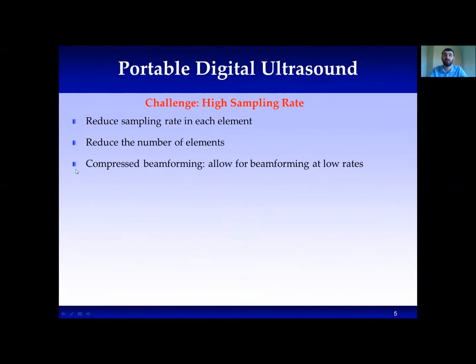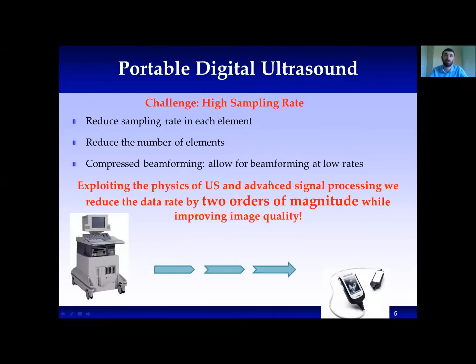However, the main challenge we encounter when trying to fulfill this vision is the sampling rate and the huge amount of data. We reduce the sampling rate at each element as well as the number of probe receiving elements, and based on the physics of ultrasound imaging and advanced signal processing, we achieve a data reduction of two orders of magnitude, as well as size reduction of the probe.